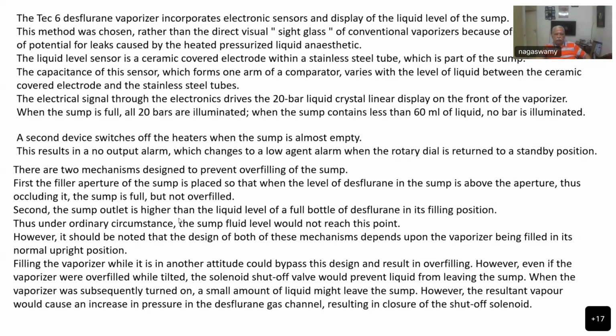Second, the sump outlet is higher than the liquid level of a full bottle of desflurane in its filling position. Thus, under ordinary circumstances, the sump fluid would not reach this point. However, it should be noted that the design of both these mechanisms depends upon the vaporizer being filled in its normal upright position. But if there is a little tilting, then the possibility of overfilling can happen. And filling the vaporizer while it is in another attitude could bypass this design, resulting in overfilling.